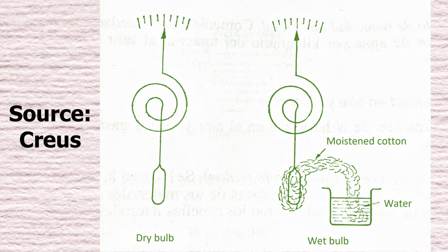Instead of consulting the psychrometric diagram for each reading, an instrument that directly measures the differential temperature between the two bulbs can be used, with which the index or the transmission signal of the instrument will directly indicate the relative humidity. The instrument has the advantage of giving great accuracy when the relative humidity is close to saturation, thus allowing the use of devices with a very narrow measuring range at RH, or relative humidity, close to 100%.